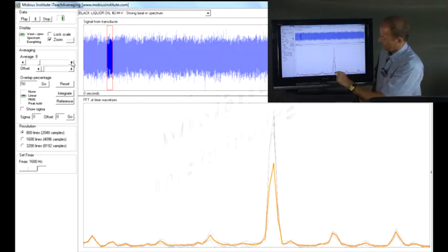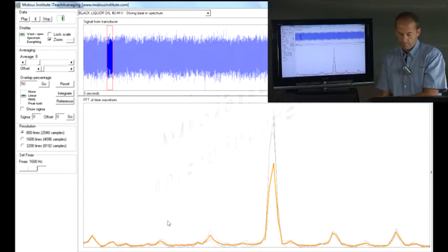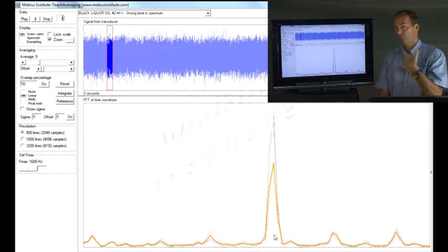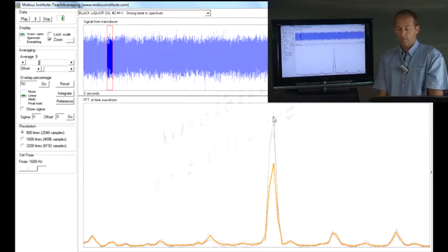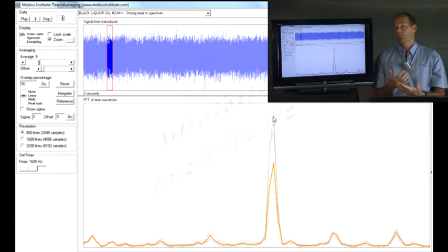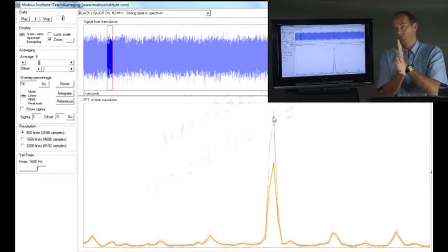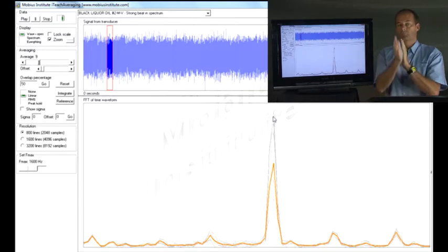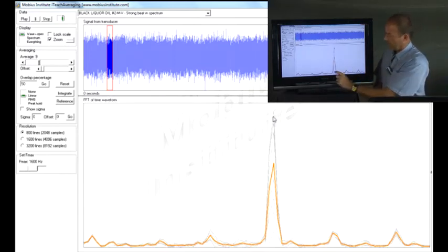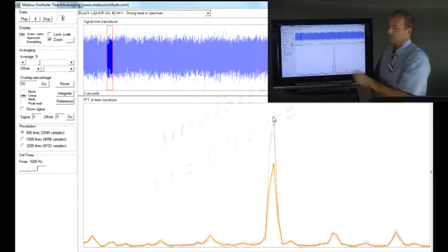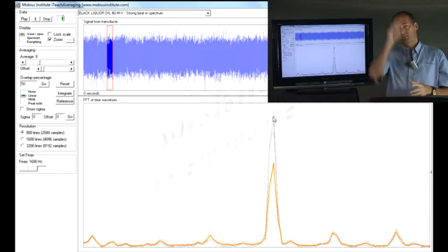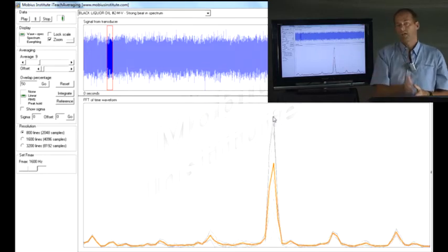Now you notice that I've got some peaks down the bottom here. There are times when there was almost no vibration generated at that frequency. When I say no vibration, there's probably two sources of vibration interfering with each other. It's beating, it's cancelling itself out and it's adding together. So it's beating up and down.